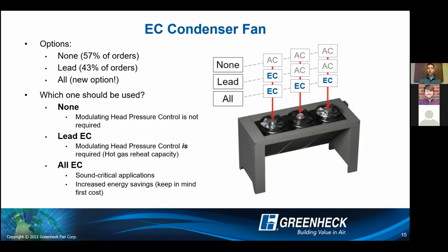So the big question we get is which one should be used and why? If you're looking at none, which means all AC motors, really that's when modulating head pressure control is not required. Maybe you don't have a hot gas reheat coil, you're not as concerned about reheat capacity or maintaining head pressure, then you can likely get away with all AC motors. Lead EC motors, where that comes into play is any time that modulating head pressure control is a concern or is required. Typically, when you're modulating head pressure control, that is only done off of the lead EC motor. It's not done with all the other condensing fans. That is strictly done with that lead. And so that is where you're looking at hot gas reheat capacity concerns.